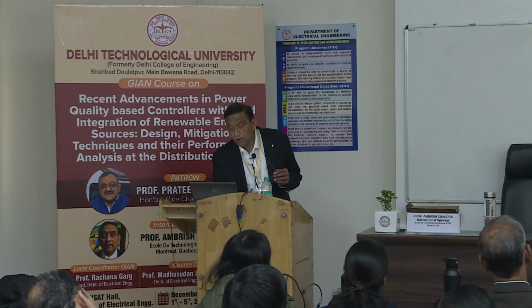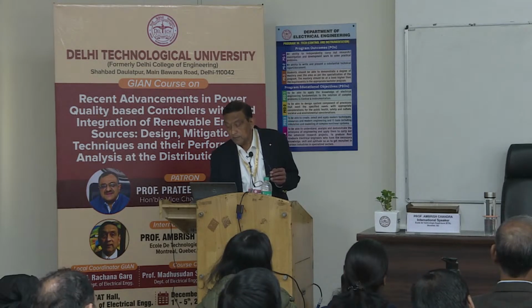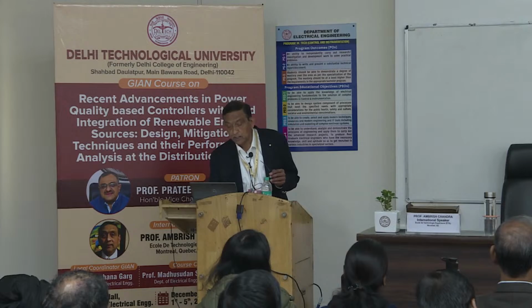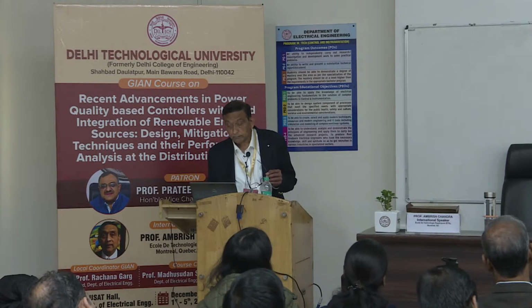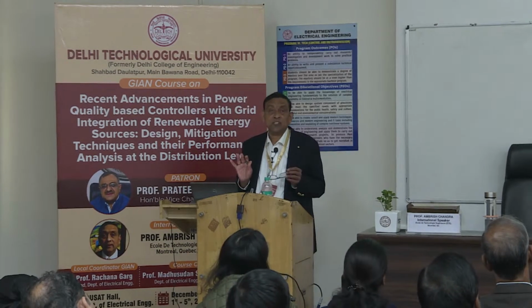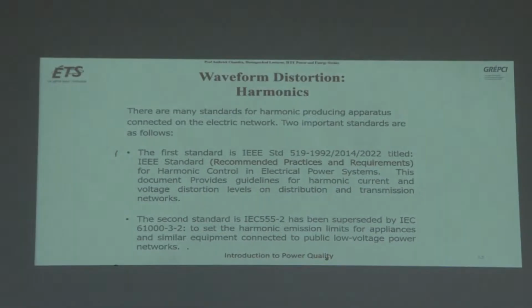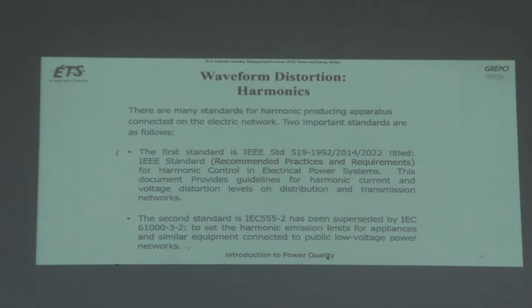There are so many problems caused by harmonics, many other problems, such as malfunctioning of energy meters and protection relays and circuit breakers. This is just one example. There are many standards for harmonic producing apparatus connected to the electric system. Two important standards: IEEE standard 519, which was originally introduced in 1992 and was a very popular standard, and that standard is still going on. They made some minor adjustments in 2014, and then again in 2022, but most things, the harmonic limits and so on, remain the same.